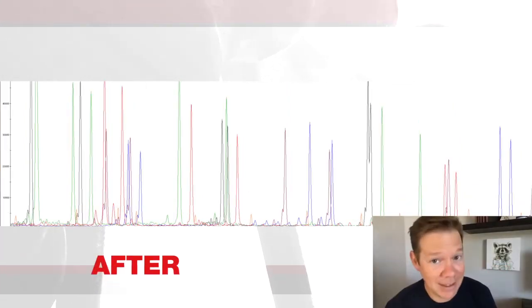Hi, this is Laura Dixon from Washoe County Sheriff's Office. How can I decrease pull-up on my Applied Biosystems 3500 genetic analyzer? The fastest way to reduce pull-up is through a spectral calibration. Pro tip: make sure your spectral calibration peak heights are similar to your sample peak heights. But if that sounds like a little too much work, the Applied Biosystems Data Collection 4 software offers a unique algorithm that drastically reduces pull-up.